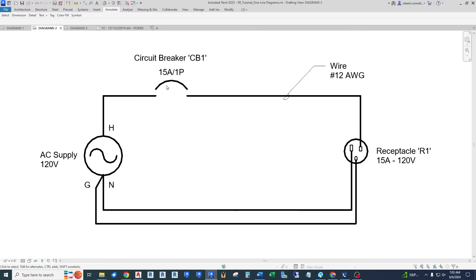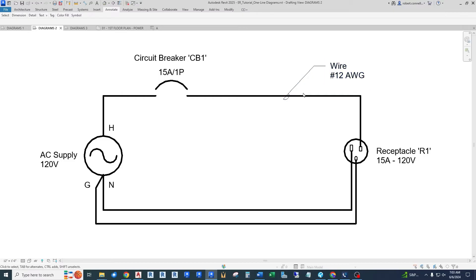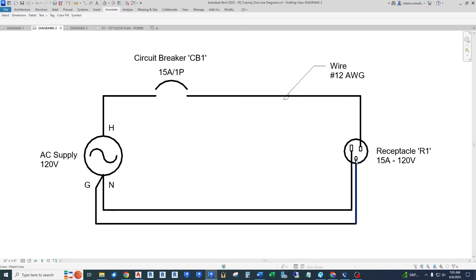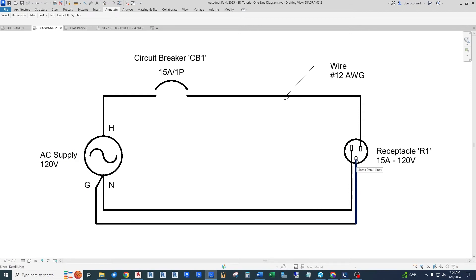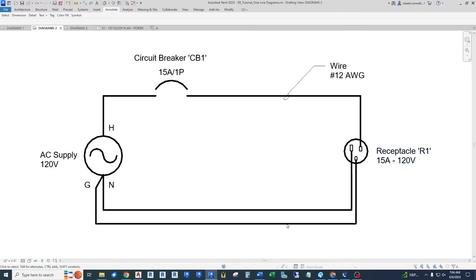We have, in this case now, a 15 amp single pole circuit breaker that protects the hot wire. We have a wire we've given a size, 12 gauge wire. And then we have just a receptacle, just one piece of a duplex receptacle. This could be a duplex. Right now it's just a simplex. But it shows the wire connected to the hot lead. And it shows neutral connected to the neutral lead. And then we even have a ground wire running alongside to connect to the ground lead. And this calls out a 15 amp receptacle. It's rated for 120 volts. And all of the pieces are called out.